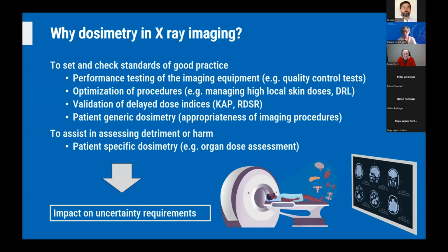Still, the dosimetry is very important in X-ray images for a number of different reasons, starting from performance testing of imaging equipment, for example, quality control test, for optimization of procedures through assessment on the local skin dose or establishing and use of diagnostic reference levels. We use dosimetry to validate display dose indices, for example, KERMA area product values or dose indices provided in the radiation dose structure report.